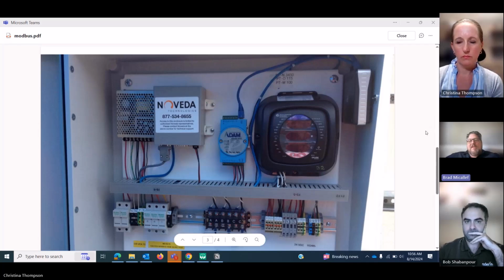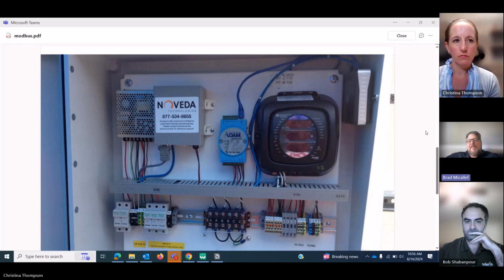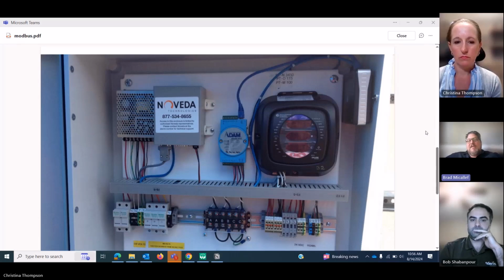What they've done here is install a protocol converter where the meter is talking serial to the bottom of that ADAM, and then the ADAM exposes the information to a network. That network looks like it's heading up to a network switch mounted in the upper right-hand corner of the box, and then ultimately it is going into this NOVEDA data logger.